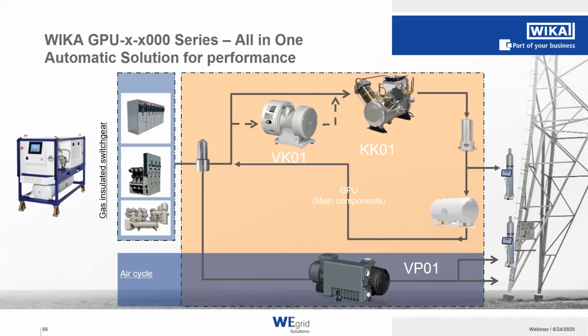This is the SF6 cycle, which you can see in the orange rectangle, and we also have the air cycle, which is running through the vacuum pump and is either evacuating the air or nitrogen from your compartment, or you're filling, so you're getting the outside air into your gas compartment.